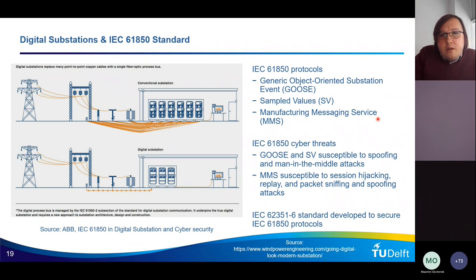So to give you a brief flavor of what sample values would do, it will just do the analog to digital conversion. So the voltages and currents will be reported to intelligent electronic devices in digital format. So we will have communication packets reporting the voltages and currents, the measurements, to the control systems. And GOOSE is a protocol that is used to send a set point to a circuit breaker to open the circuit breaker so that the transmission line, in this case, can get disconnected.